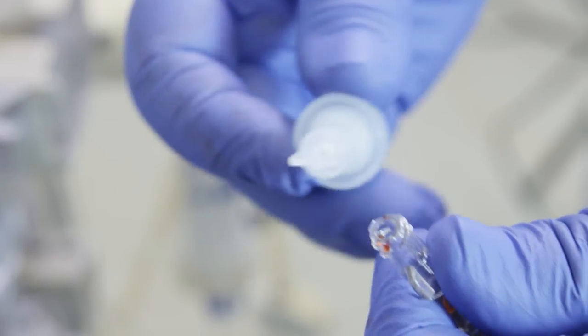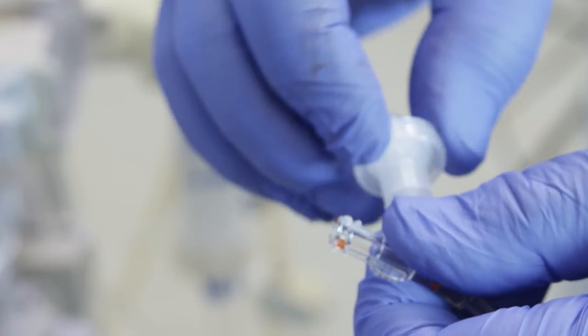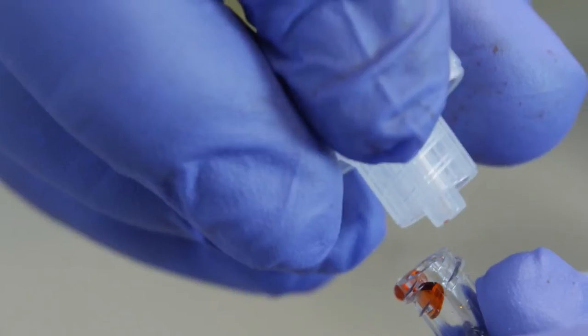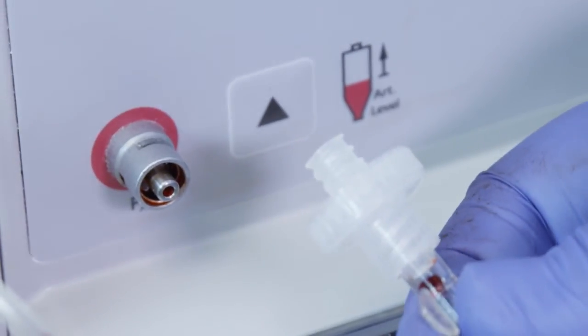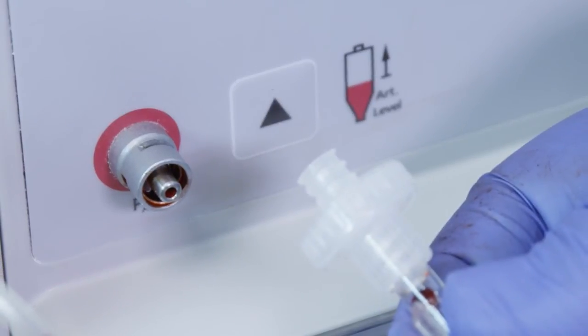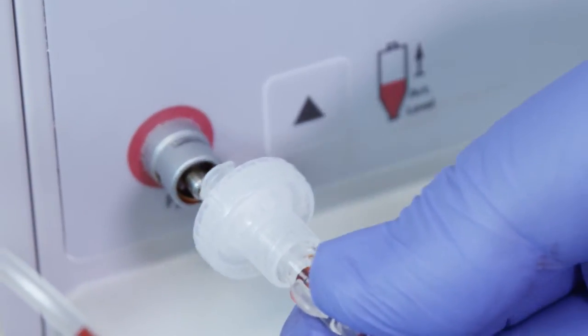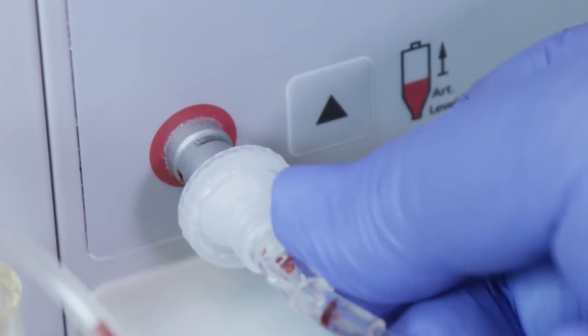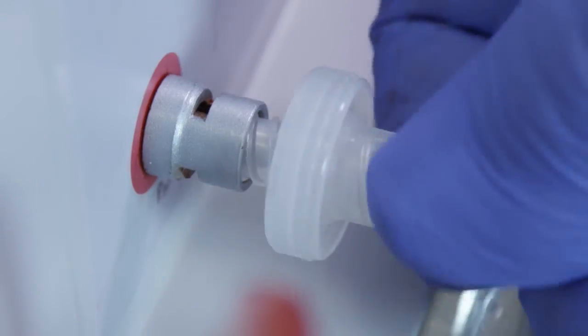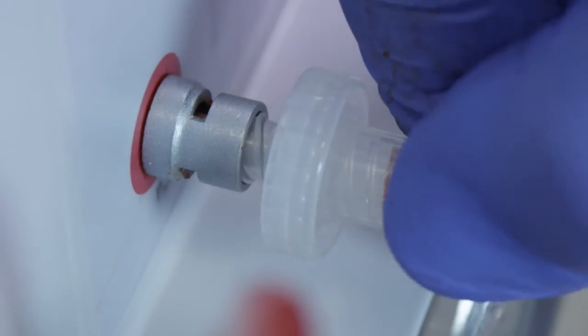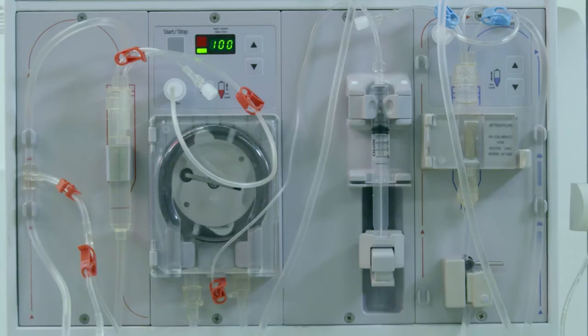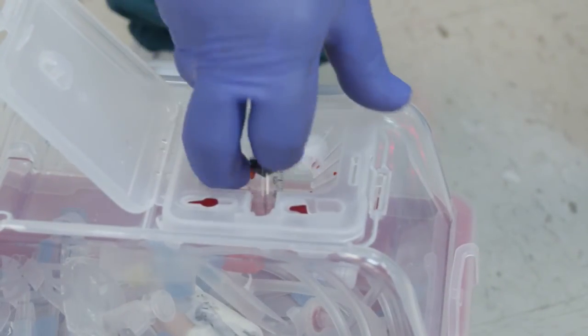Remove the protective cap and aseptically attach the blood tubing pressure monitor line to the transducer protector male luer lock fitting. Securely tighten with a twisting motion. Do not remove the new transducer's protective cap until ready to connect the blood tubing set. Attach the new transducer protector female luer lock fitting to the machine's male luer lock in the transducer port. Securely tighten with a twisting motion. Continue with the clinical setup and treatment per the physician's prescription. Dispose of the wetted transducer protector.